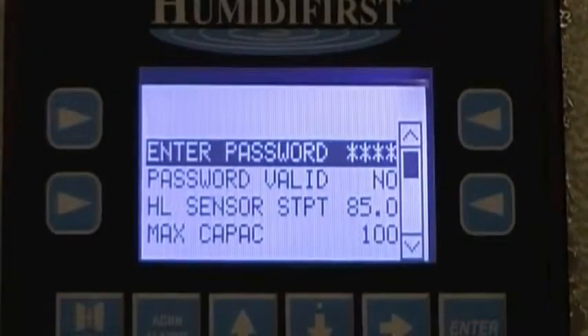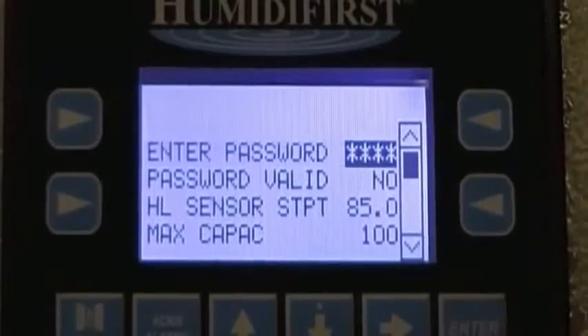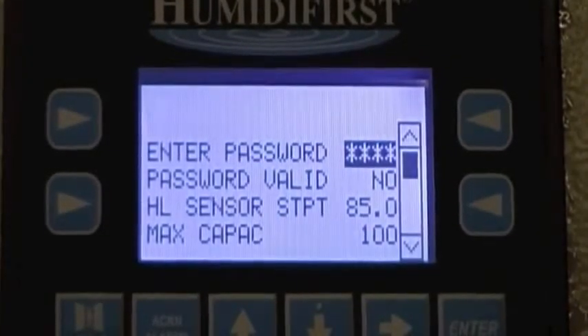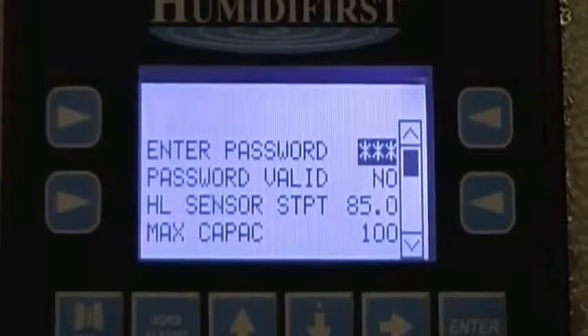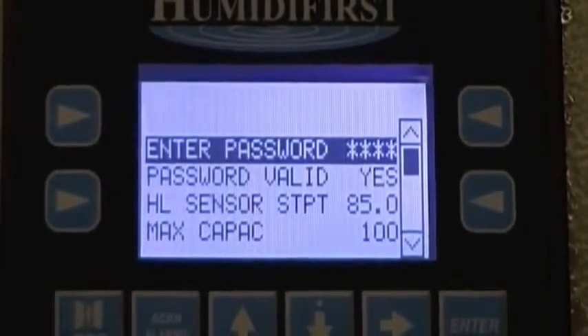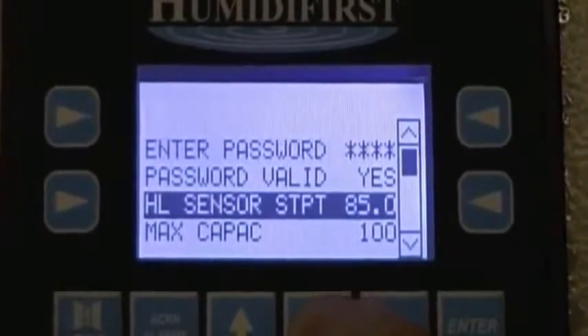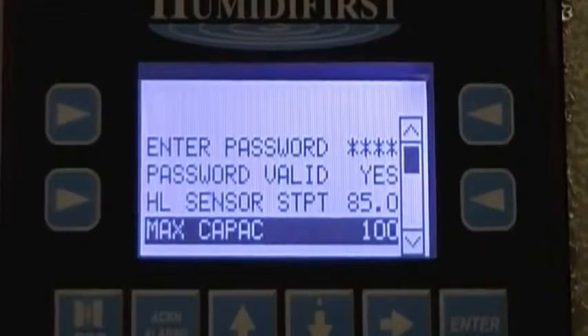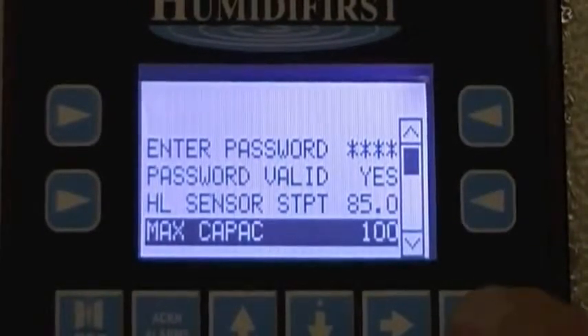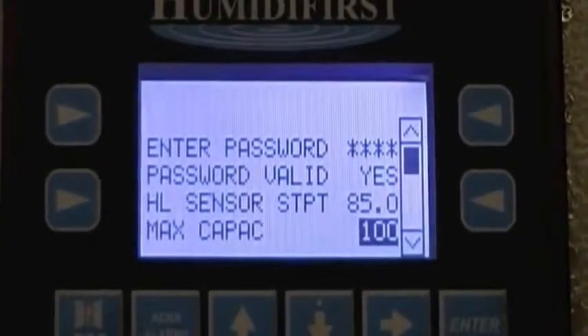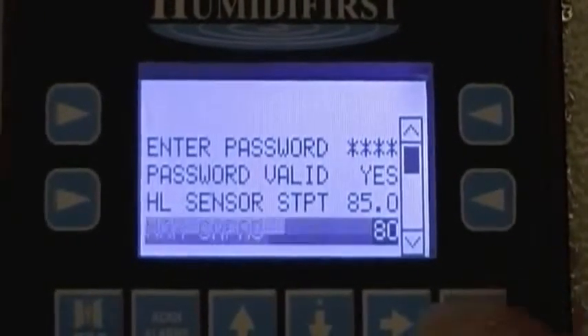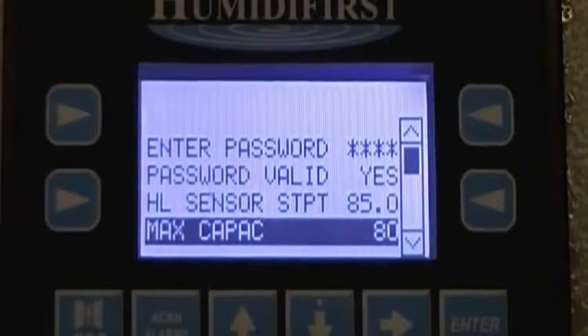The first thing you must do in this screen is enter your password. Press enter until only your asterisks are highlighted. I will enter my password of 4444 and press enter. The system will say password valid yes. You may now alter your set points. In this case, we will take the maximum capacity of the humidifiers from 100% and change it to 80. Highlight max capacity, press enter until only the 100 is highlighted. I will then enter 80 and press enter. The humidifiers will now run at a maximum capacity of 80% no matter the BMS signal.